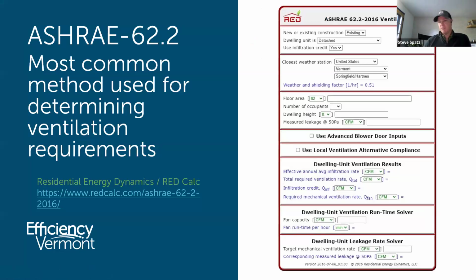But how do we get to the point of knowing what to design for? So this is the ASHRAE 62.2 standard for defining ventilation rates for residential construction. There is a tool available online called the REDCalc tool. And this is just a web-based tool that you can go to and enter in your data points for the building that you're building. And this tool will do the ASHRAE calculations for you, and then give you what your required ventilation rate needs to be for that specific building.